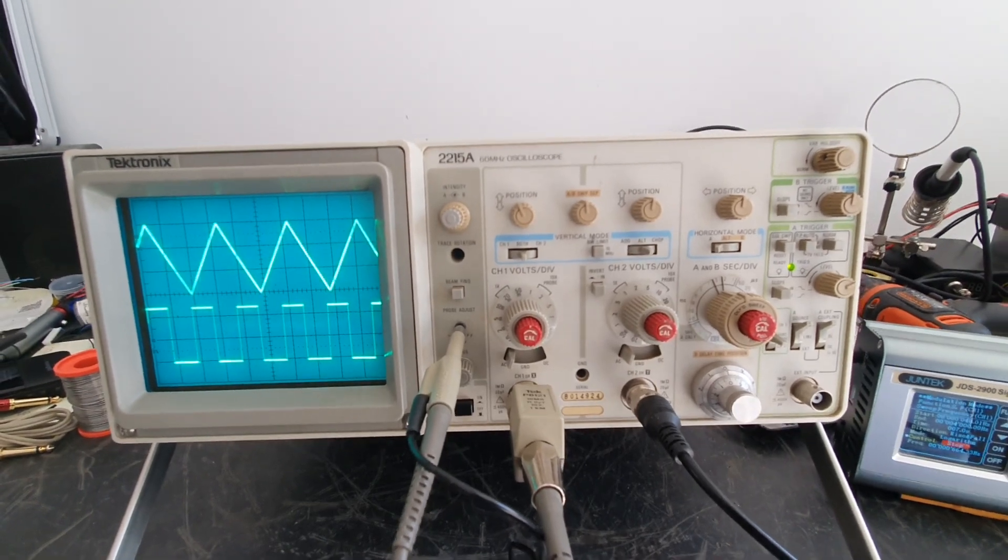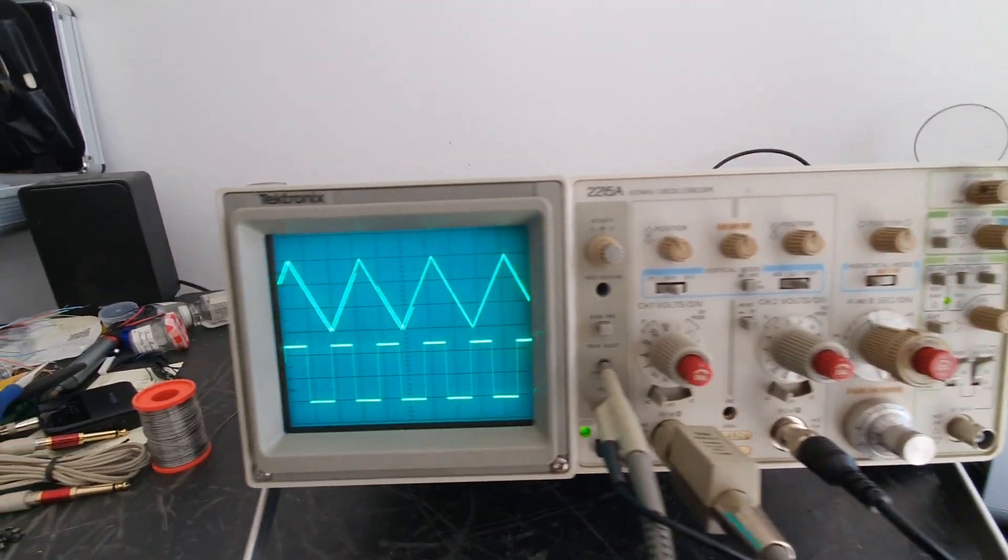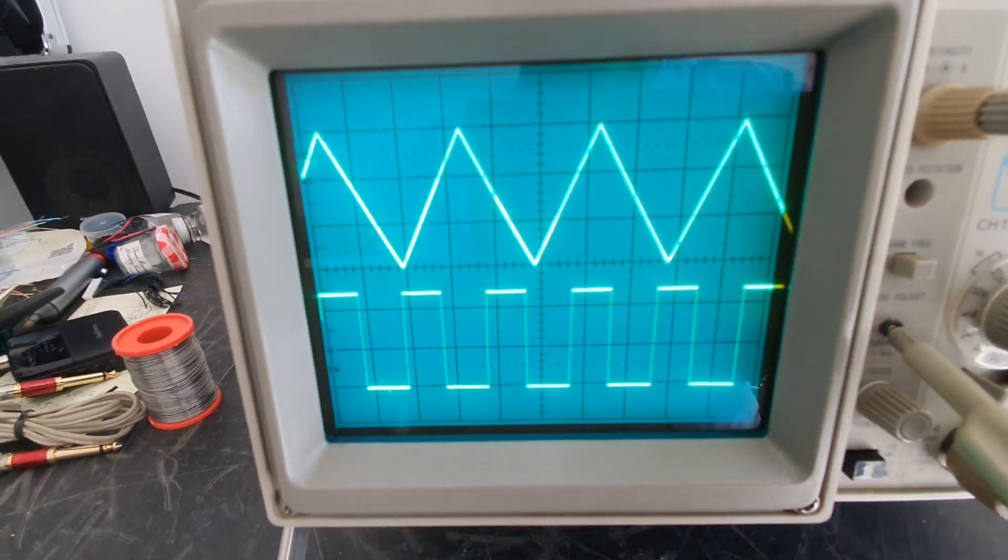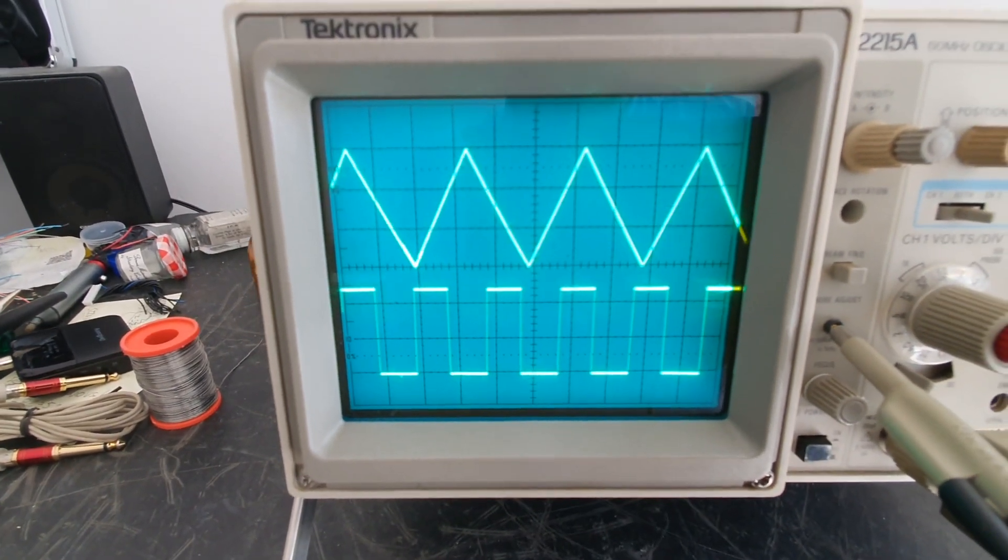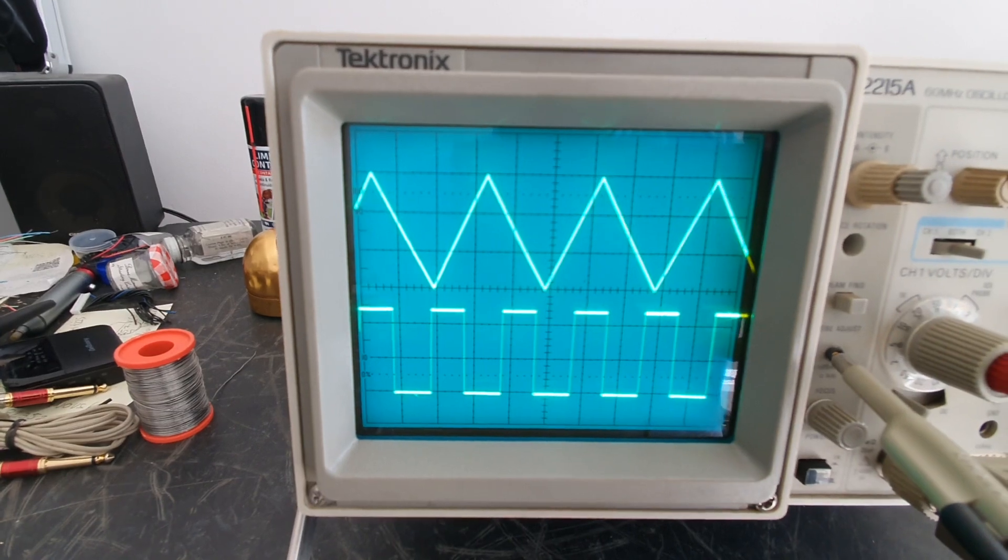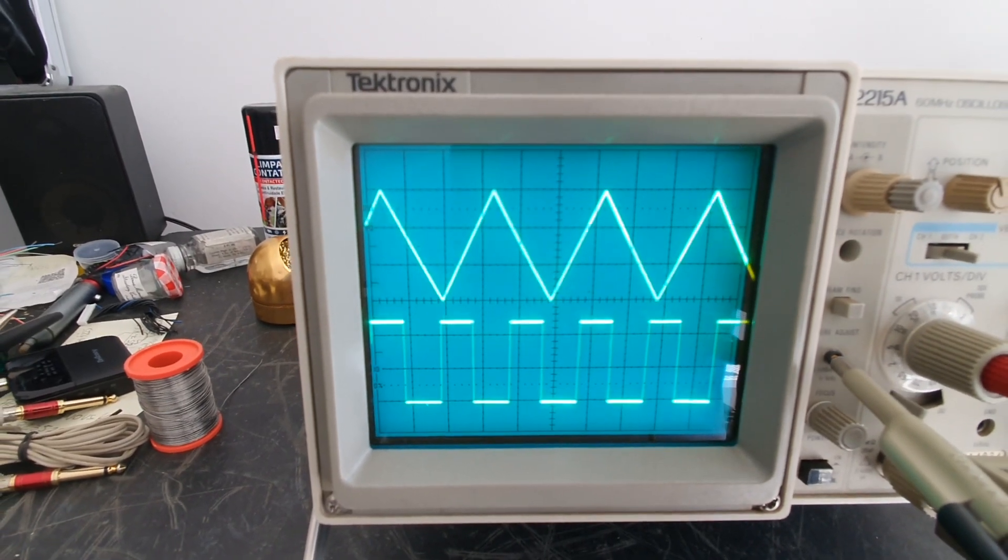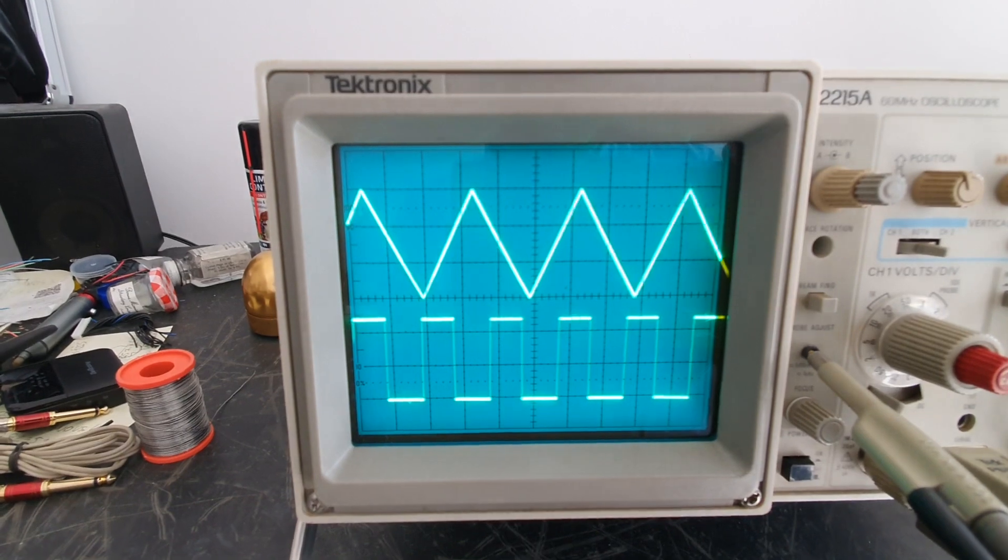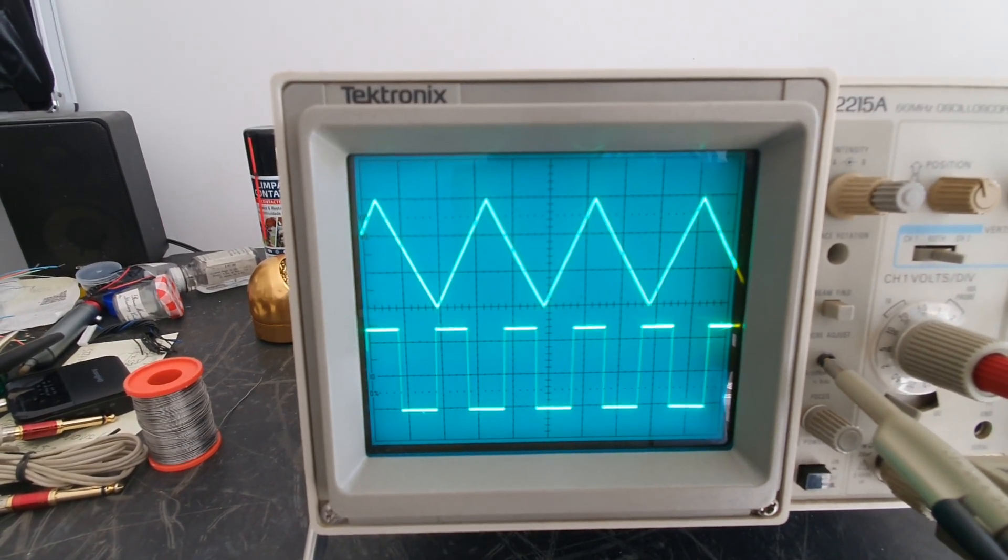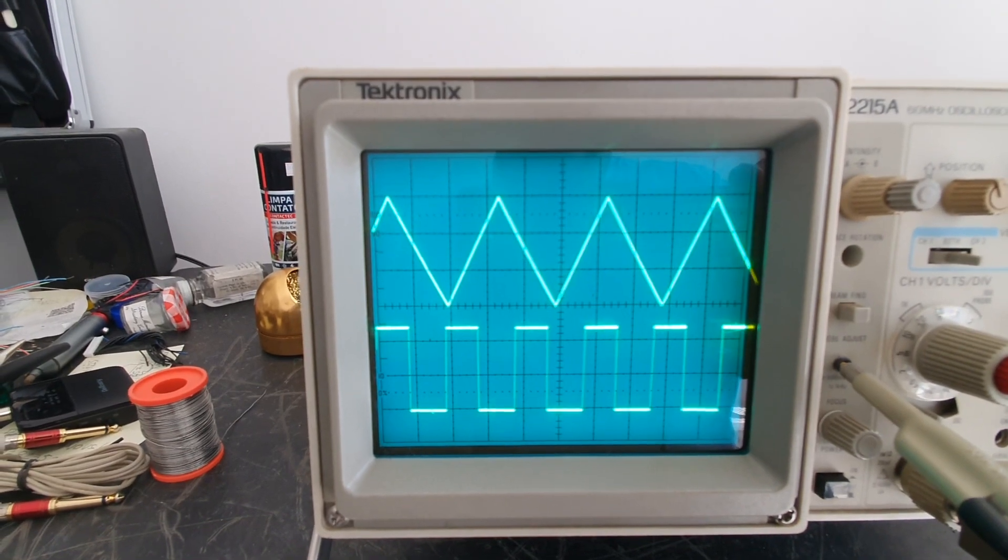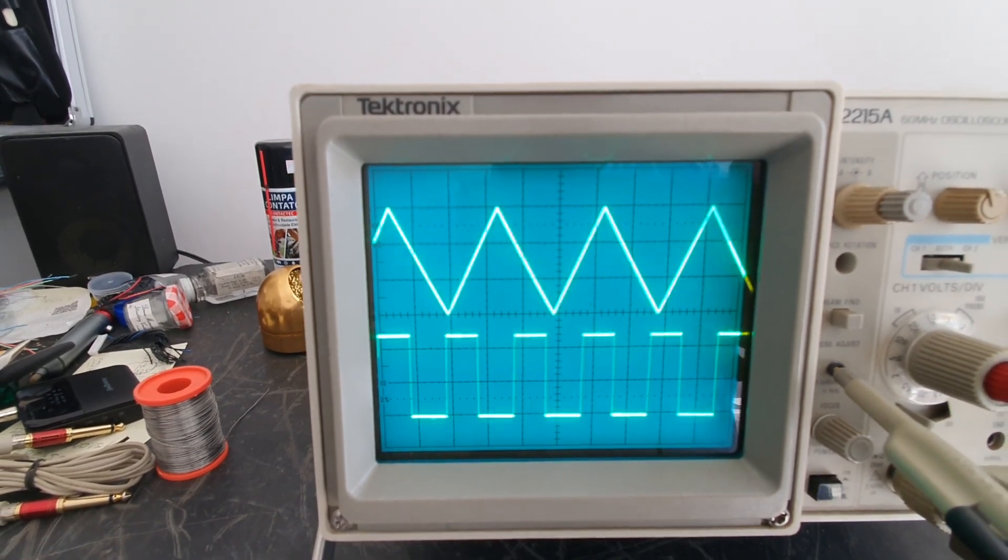When you are buying an analog scope with a CRT display you want to obviously check the CRT display and make sure there's no burning in it. So if I was to leave this triangle wave and square wave here for a few days like that, it could actually burn into the phosphorus and I get a permanent reminder of the signals I was looking at.